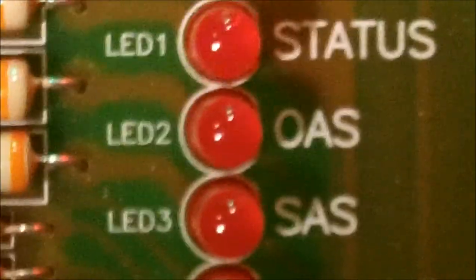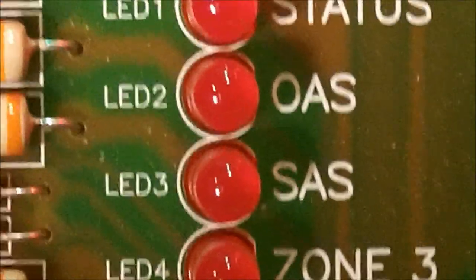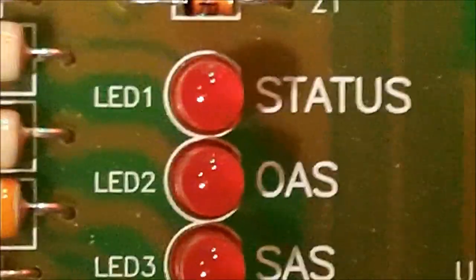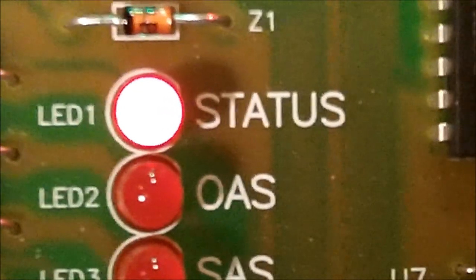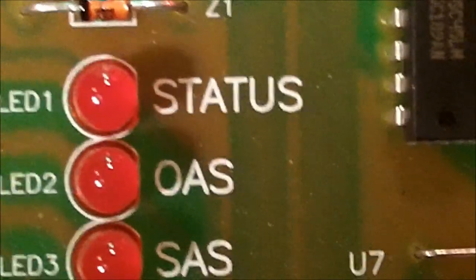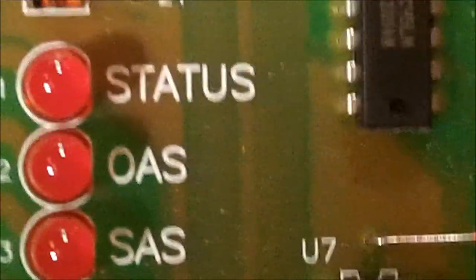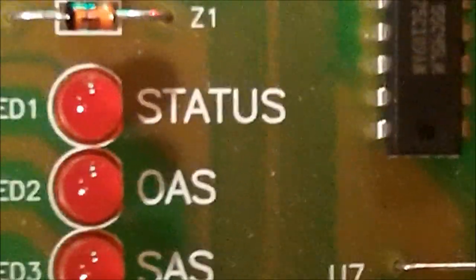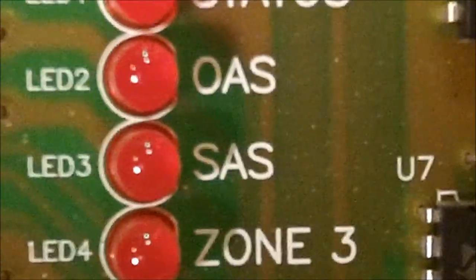The first one, of course, is your status light, and it's constantly checking. They have what they call a watchdog circuit, and every time that thing is turning off and on, it is checking the control board. So every second it's making a check of everything that's happening on this board. The next light is your outdoor sensor.